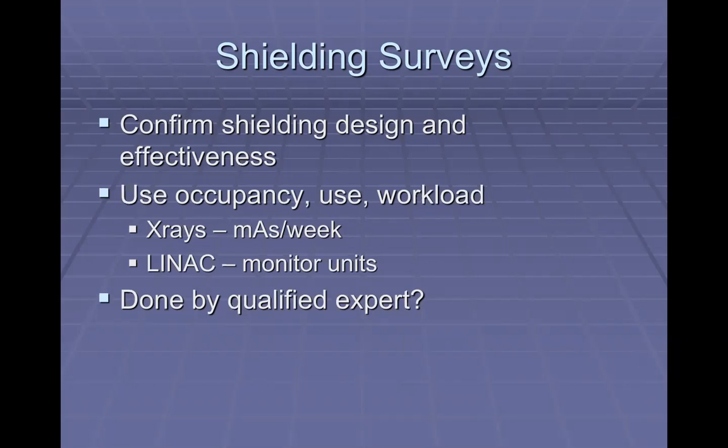They're going to be one of the first things that an inspector looks at when they come in for a LINAC inspection. We kind of have perpetual surveys in the regard that we have workers constantly around these machines, constantly around these vaults, and those dosimeters are also read very closely. So beyond our one-time survey of the vaults, we also have ongoing information that lets us know that the people that are using these machines are not at any sort of serious risk from radiation.